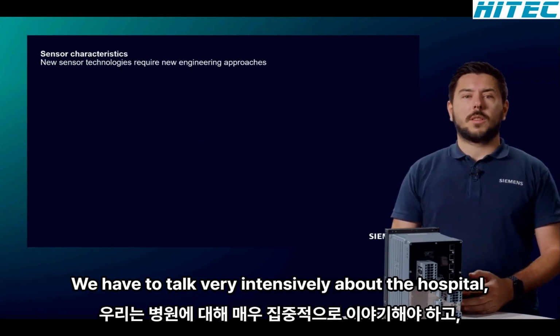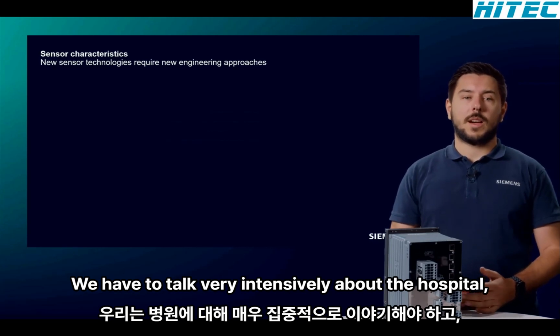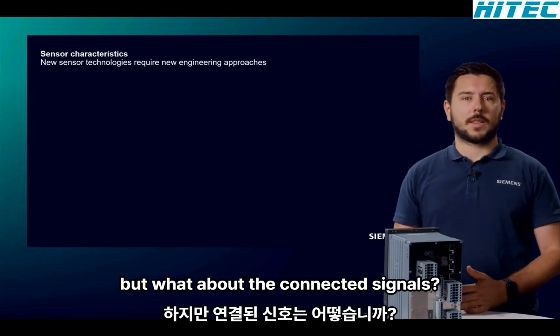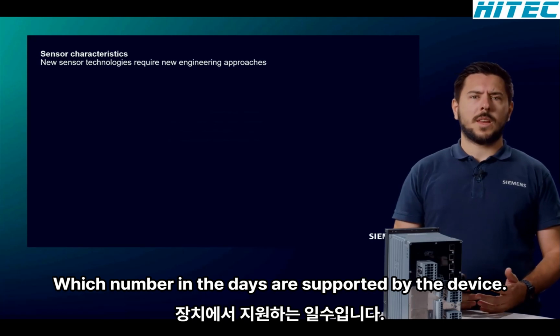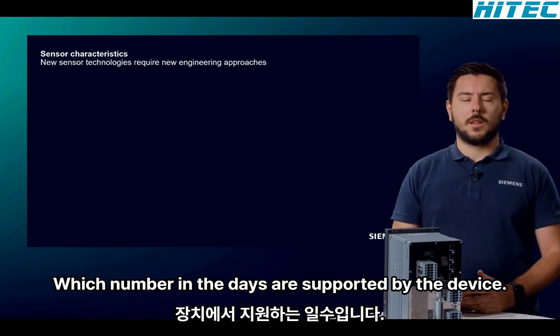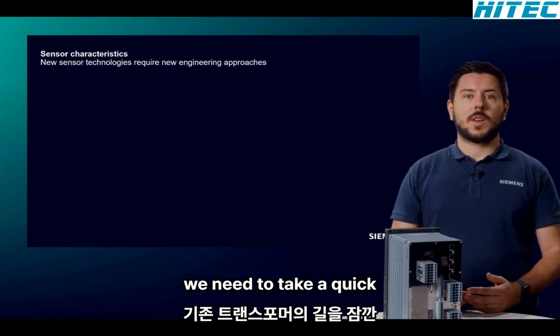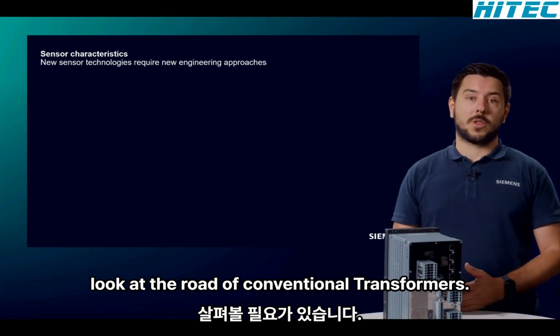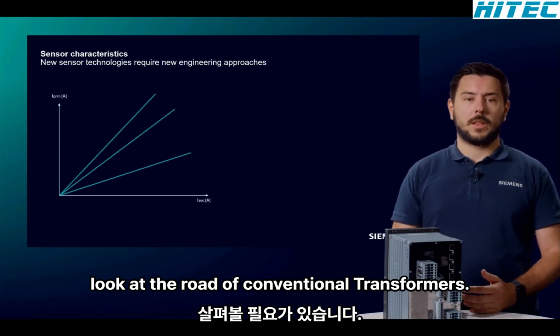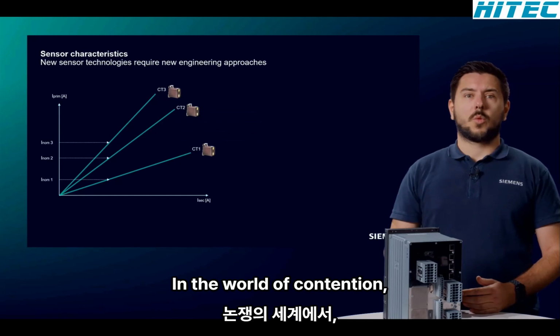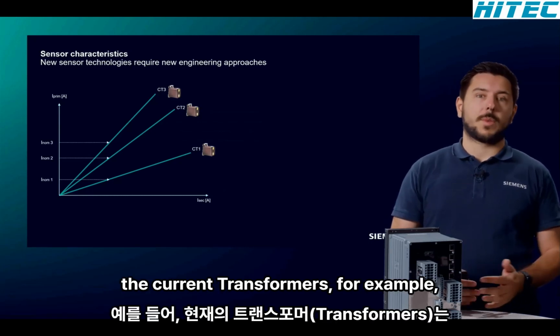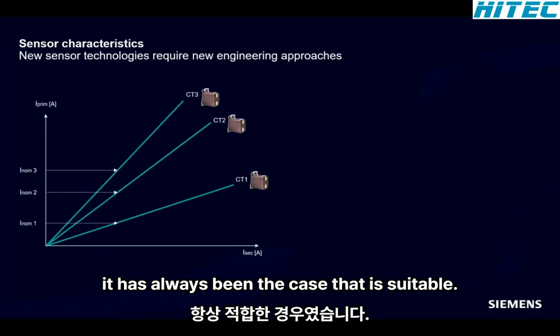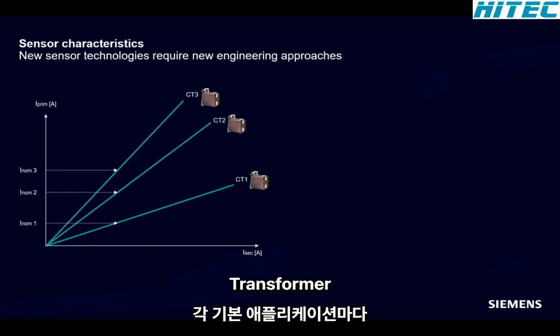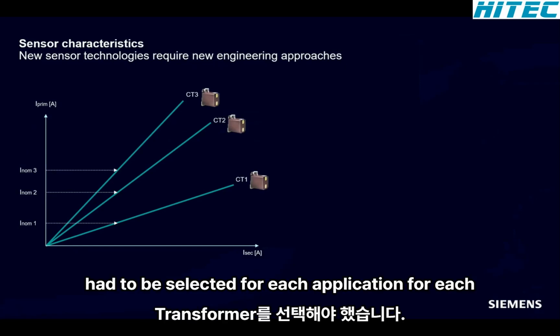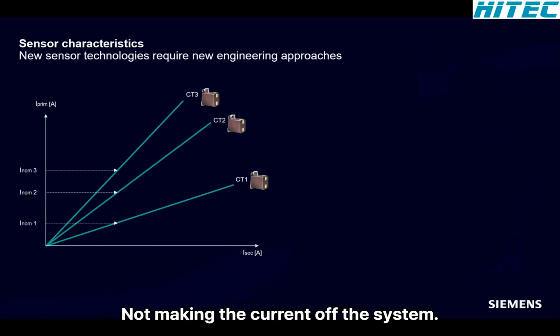Now we have talked very intensively about the hardware, but what about the connected signals? Which nominal values are supported by the device? To explain this, we need to take a quick look at the world of conventional transformers. In the world of conventional current transformers, for example, it had always been the case that a suitable transformer had to be selected for each application, for each primary nominal current of the system.